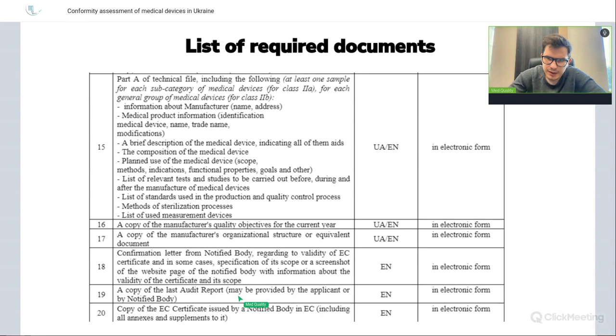A few words about these agreements between the European notified body and the Ukrainian conformity assessment body. We have the law of Ukraine on technical regulations, where Article 45 states that a Ukrainian conformity assessment body may accept the results from a European notified body based on an agreement. And this agreement is a so-called unilateral recognition agreement because it is only one-sided. The Ukrainian conformity assessment body recognizes and accepts the result of conformity assessment which was conducted on the territory of the European Union.